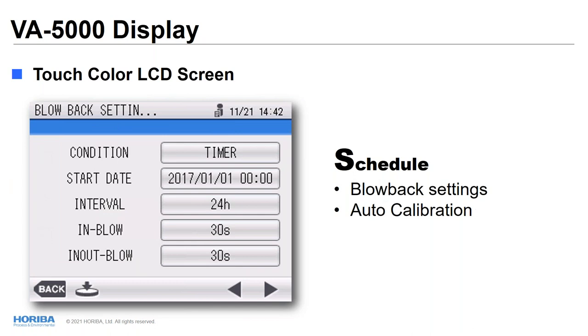In the menu, there are setting modes. You can schedule blowback timing. This is used to put air in the probe and back toward the sample point, so that the dust collected on the filter goes back to the process. This function always helps the performance of the probe filter and makes the lifetime longer for the probe and the pump. You can schedule the starting date, time, and interval, and how long you want to blow. So it's pretty flexible, depending on your conditions.